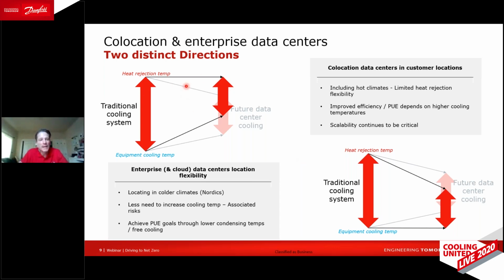With co-location data centers, they're much more focused on increasing the cooling temperature, because they have to be located near their customers—including places like Phoenix Arizona, Rome, Guangzhou, or Singapore—where there's limited capability to drive down the condensing temperature. So they focus on increasing the cooling temperature to drive better efficiency and lower differential temperatures. As opposed to that is the enterprise.